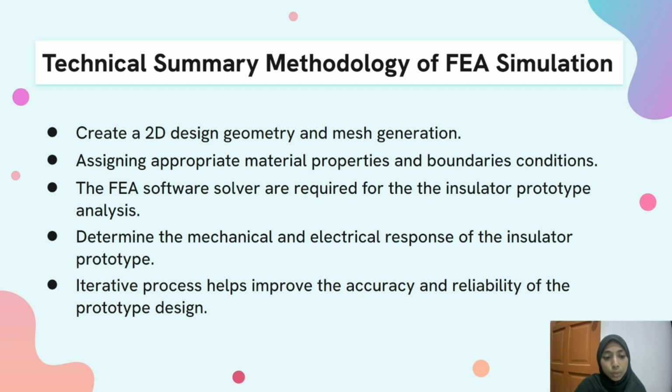Next, we determine the mechanical and electrical response of the insulator prototype. This includes solving a system of equations that defines the behavior of elements and their interconnection. The results of the investigation include voltage gradient, electrical field intensity, stress distribution, and more.